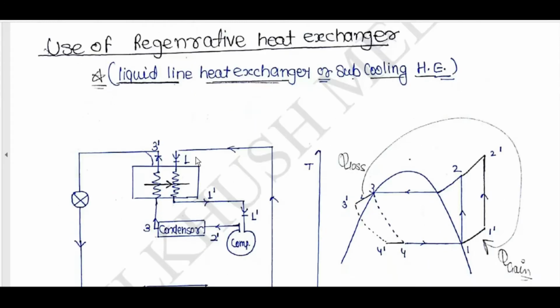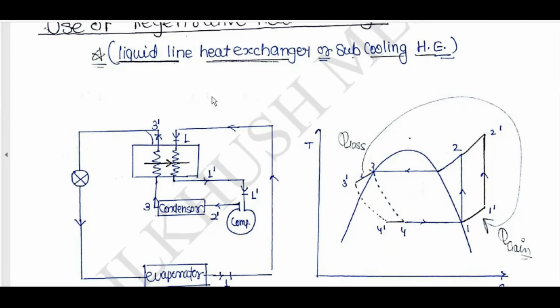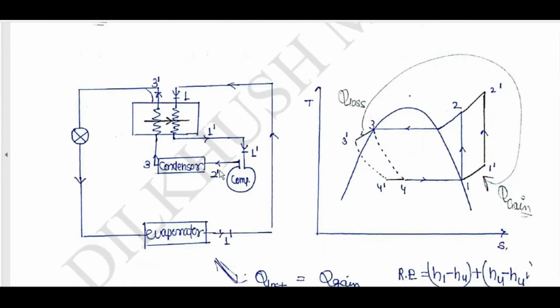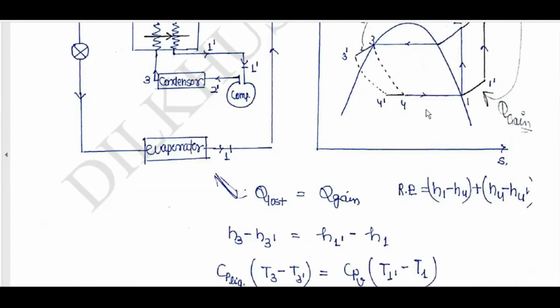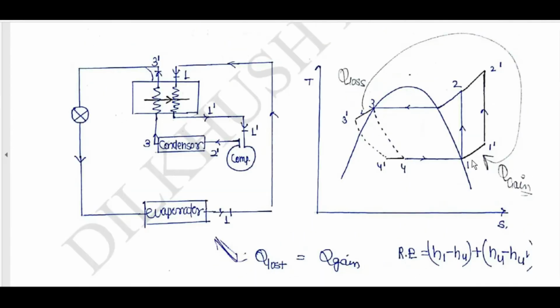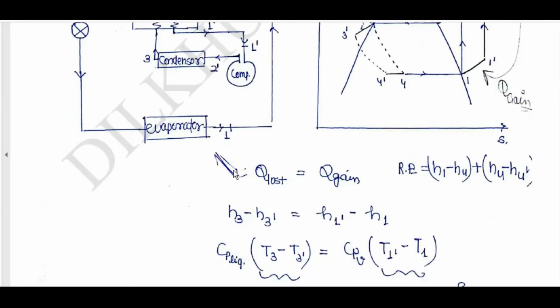Use of a regenerative heat exchanger, also called a liquid line heat exchanger or subcooling heat exchanger. Compressor, then condenser, then it flows through a heat exchanger. After the evaporator, it then flows through the heat exchanger. Here Q lost is used for Q gain. Q lost is equal to Q gain.